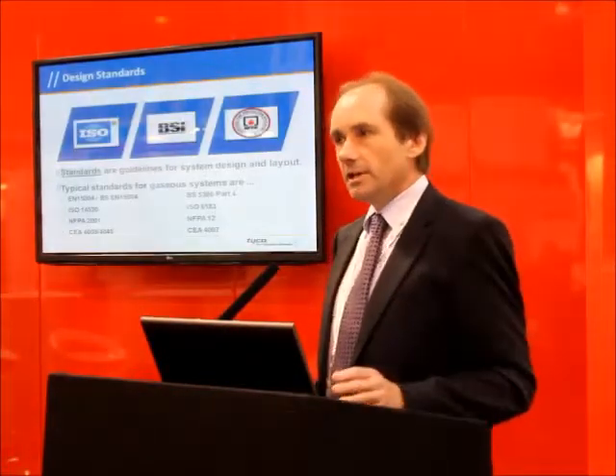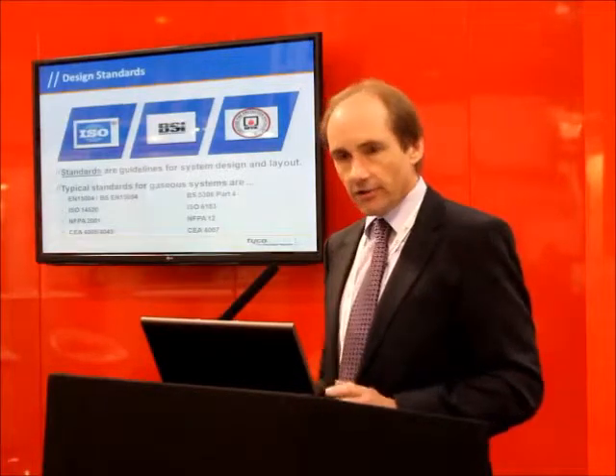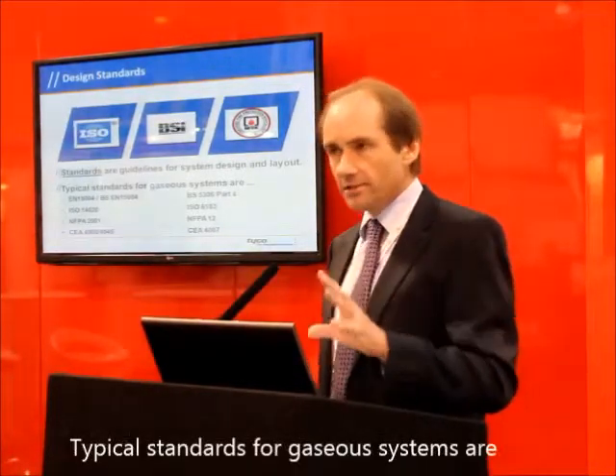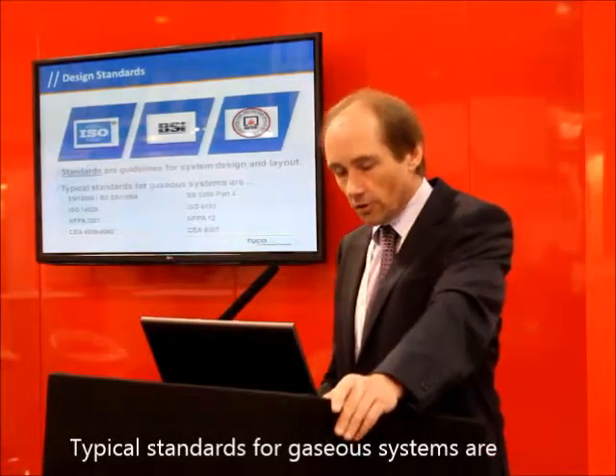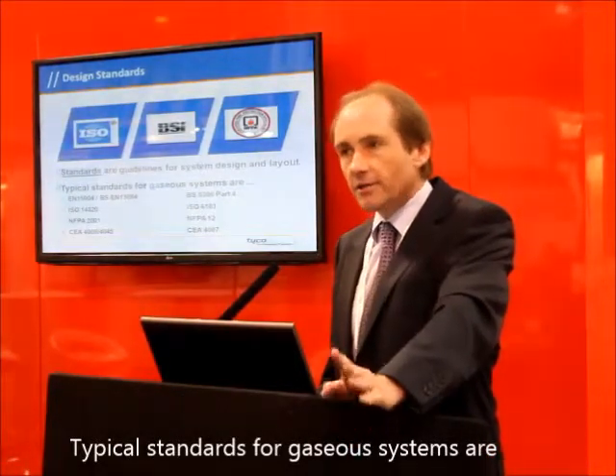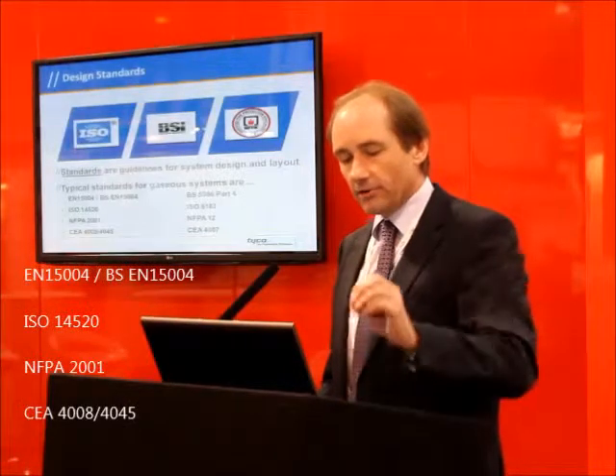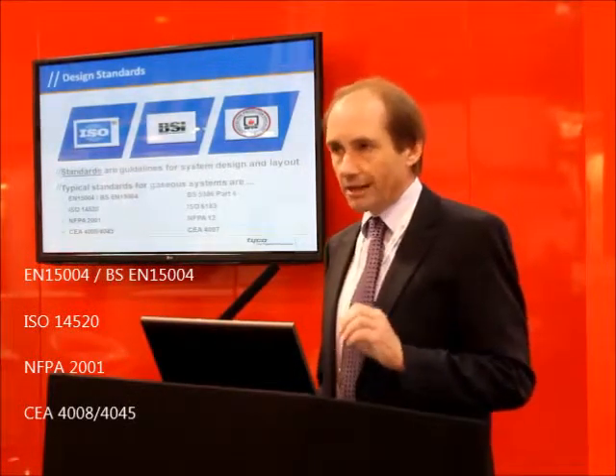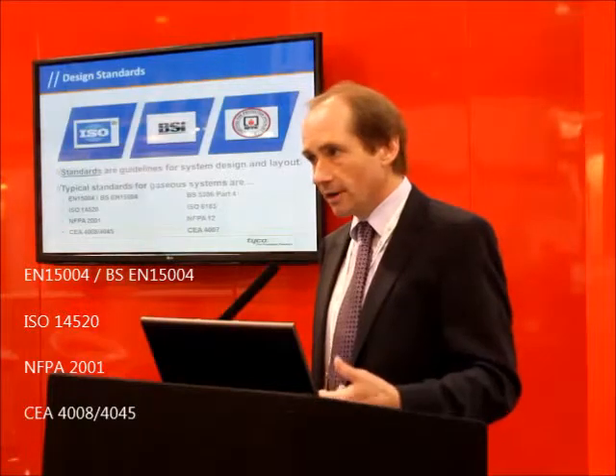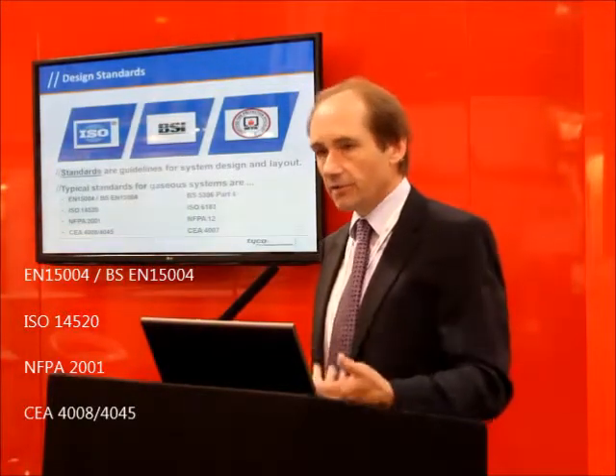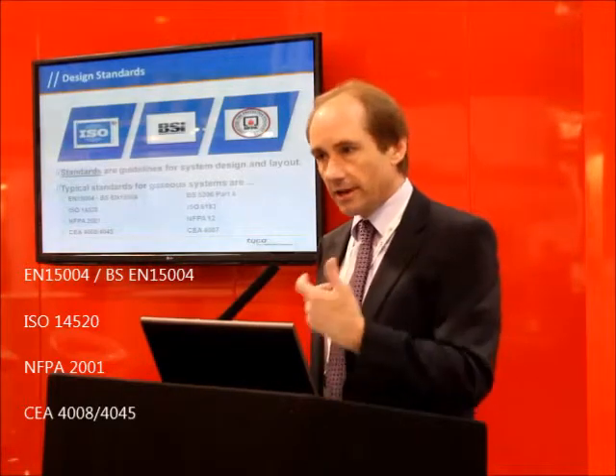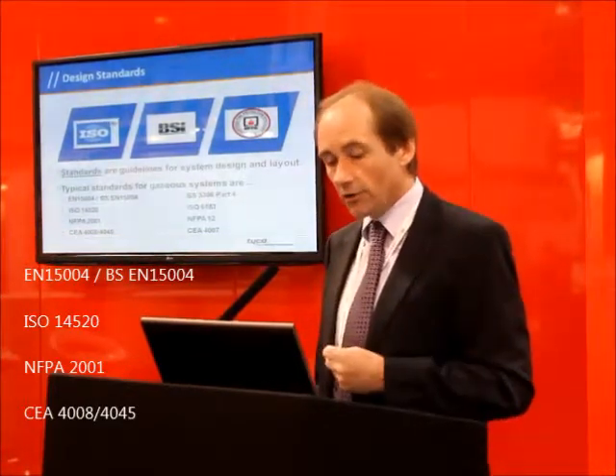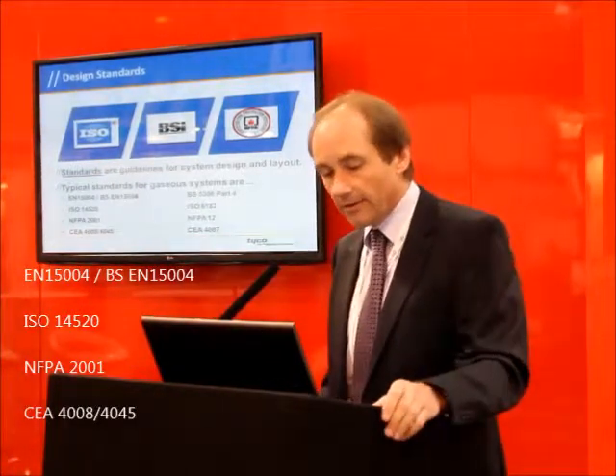When we look at the overall design of a clean agent system, we need to focus on the various standards applicable across the world. The standards on the left-hand side are those traditionally associated with true clean agents — the halocarbon group, typically FM200 and NOVEC 1230, and the inert gases: Inergen, IG55, IG01, and IG100. Those are covered by that group of standards.